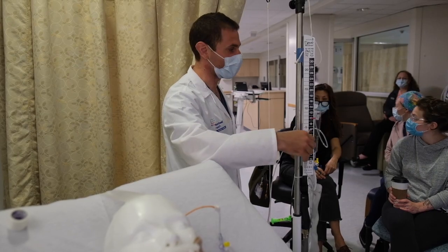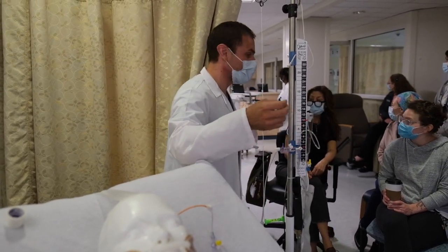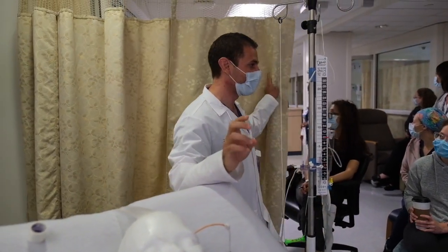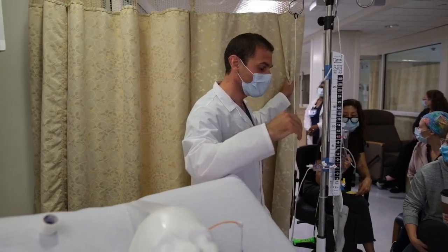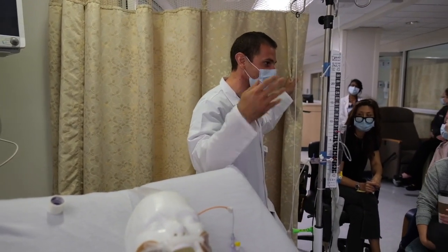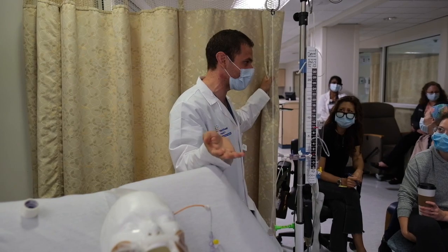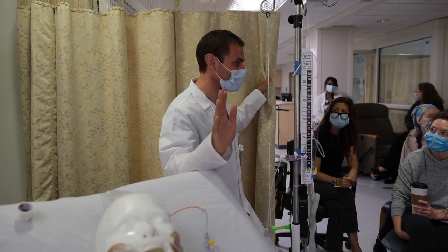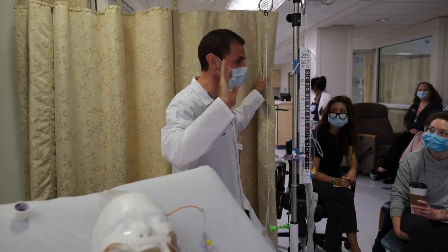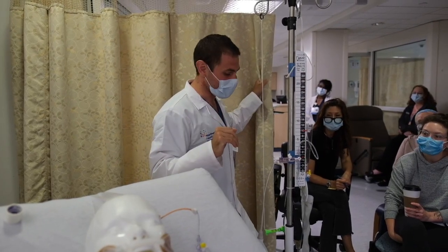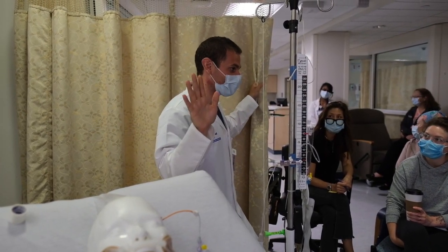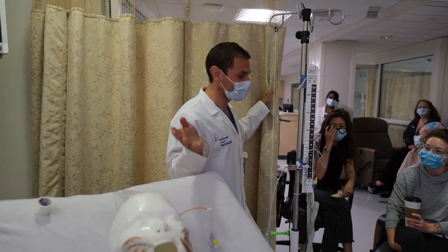And the slightest turn of a stopcock or anything else, pieces would just snap off. And the whole system would be open, people were leaking CSF, and it was sometimes happening randomly without people even in the room. So we don't use that particular system anymore.